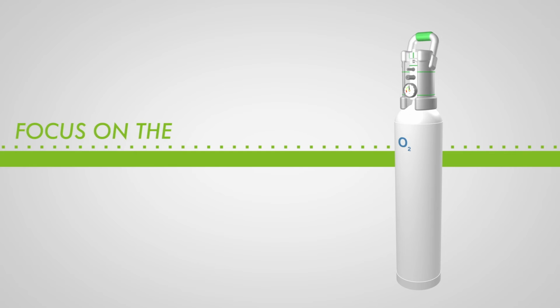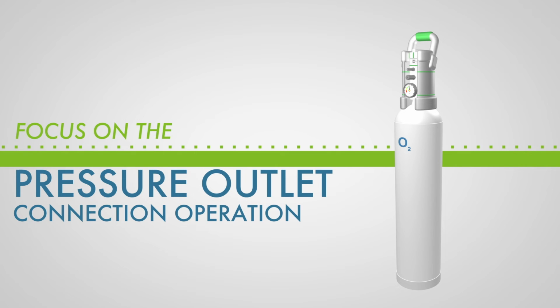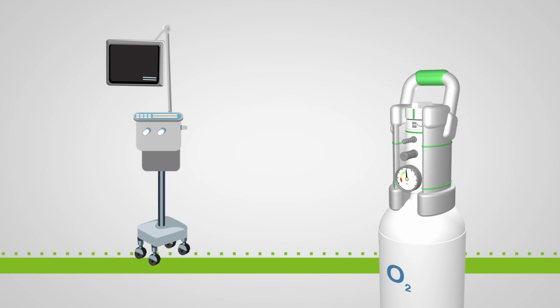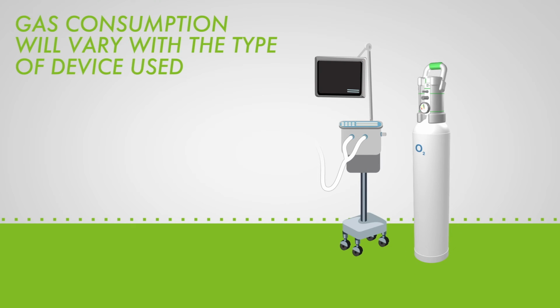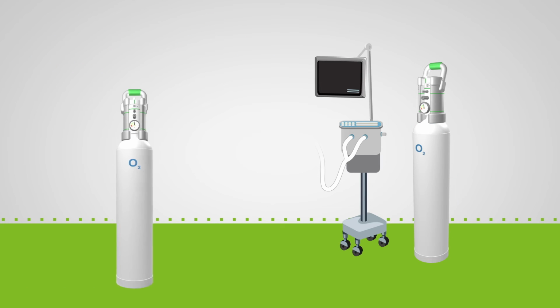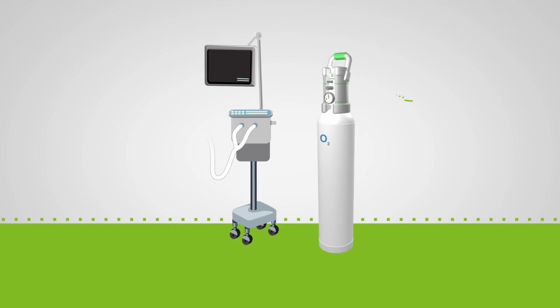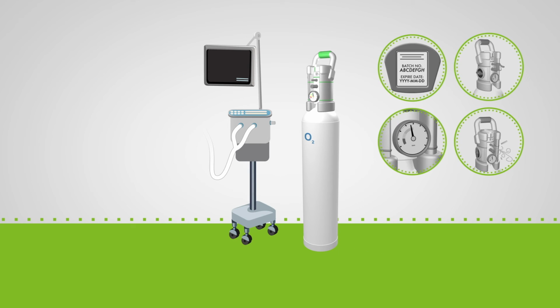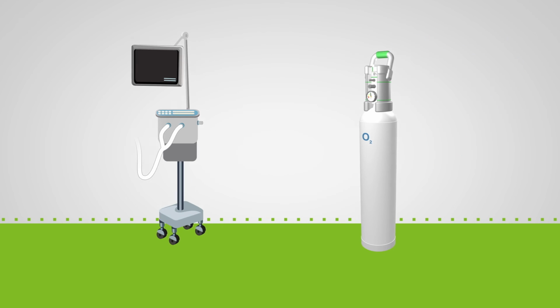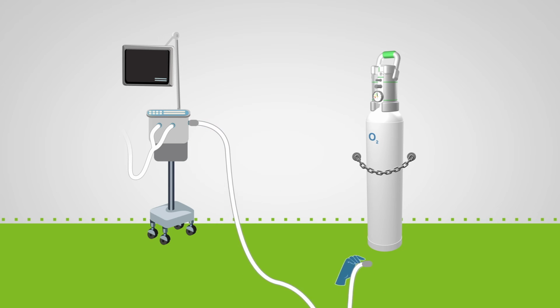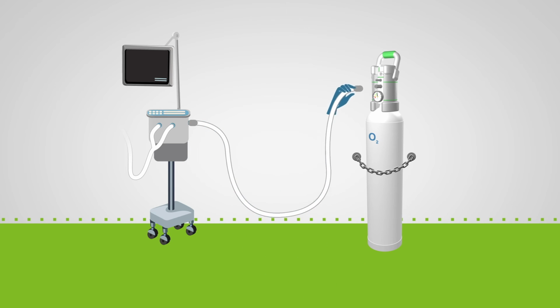We will now focus on the operation of the valve using the pressure outlet connection, used to supply oxygen to a separate medical device. As the gas consumption will vary with the type of device used, it is wise to start with a full cylinder and to always have a backup cylinder ready. Having successfully checked the valve is working correctly, as described before, connect the hose first to the medical device and then insert the probe into the pressure outlet. Verify that there is no audible leak from the connections. Then you can turn on the separate medical device.